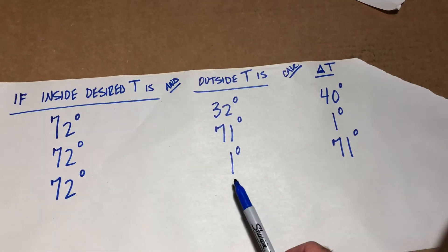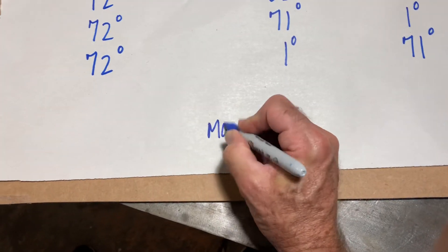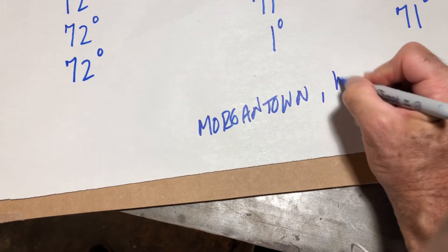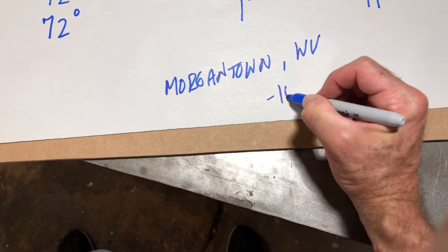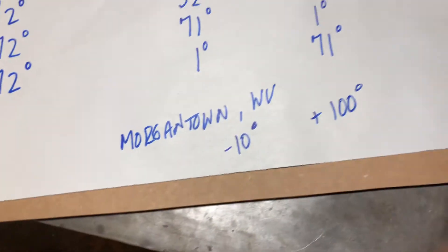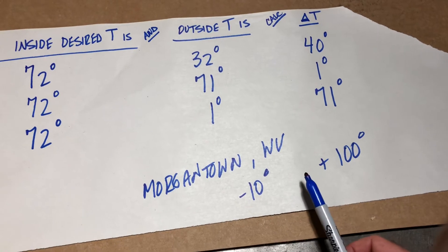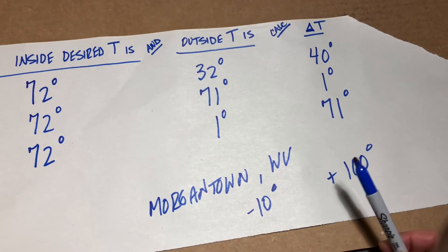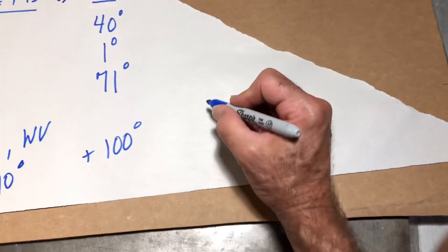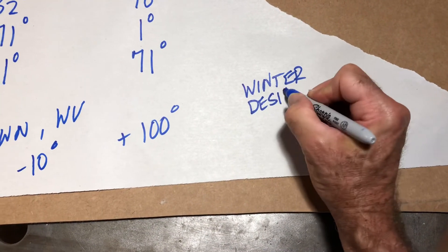Now, with all these different temperatures, which one do we use? So let's say Morgantown, West Virginia, where this course is being taught, has a lot of temperature variation. In the winter we might be down to minus 10 degrees, in the summer we might be plus 100 degrees. So what is our delta T? Well, it depends on what time of year we're thinking. And since we're going to be looking at heating, we're going to assume a cold season, and we're going to use a thing called the winter design temperature.